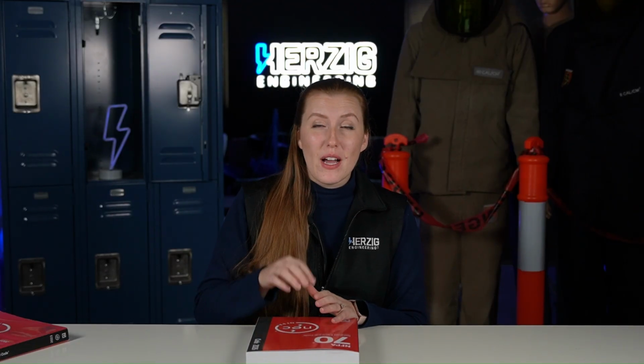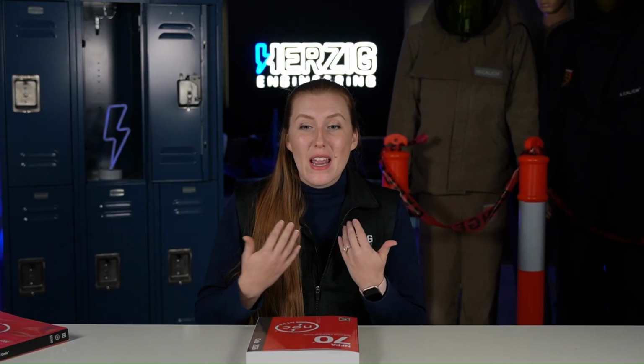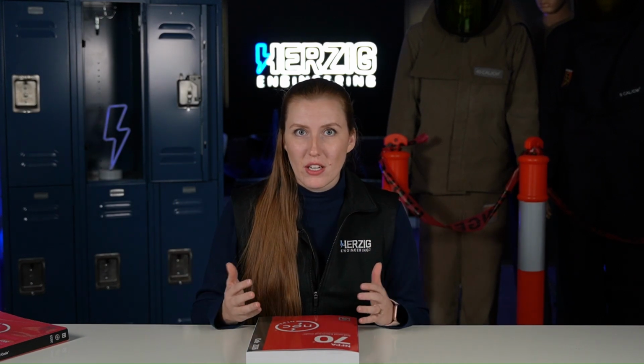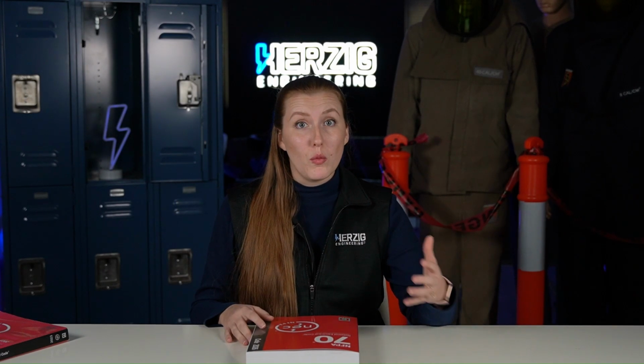A lot of states, if they are to adopt the latest edition, wait till the beginning of the year for that code release. So January 2026, for several states, for several of you, that's whenever you're going to have to be able to comply with these clarified arc flash hazard marking requirements. Again, in my opinion, looking at the history of our codes and standards and going to different meetings and reading through the different markups, this has been the intent for a long time. But no more loopholes, no more guesswork. It has been clarified in black and white. Now it's required for much more equipment and much more detailed.